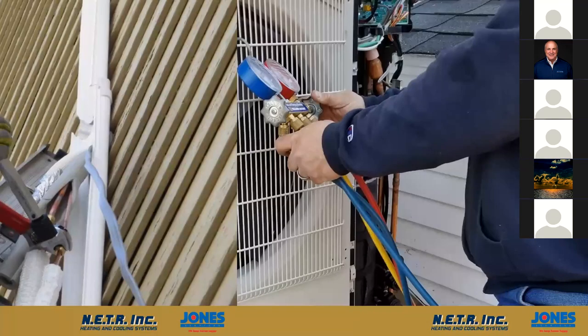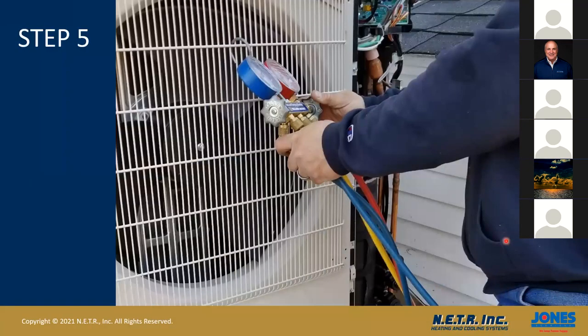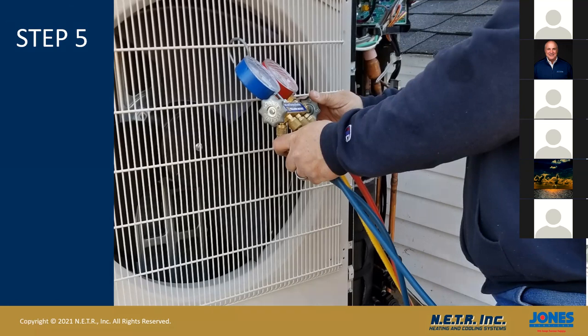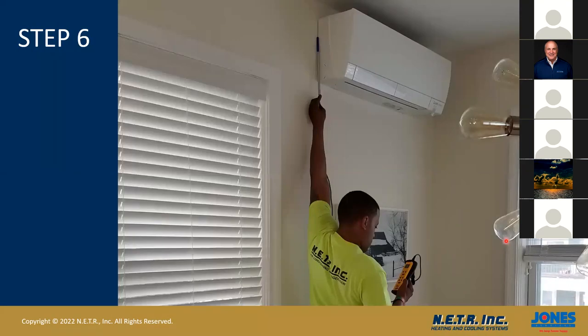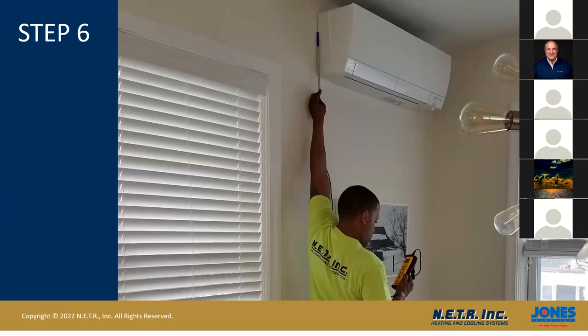Step five is the evacuation and the charging of what's going to happen. You're going to see a technician pressure testing things and monitoring pressure to make sure that the lines hold the pressure. You're going to also be seeing, again, here's that high efficiency unit that the gentleman hung. You can see he's doing some testing of air. Some return air temperatures, you can see right here. Here's that little sensor I was talking about. You can see he's measuring some temperatures in the room. So that's your six-step process on a one-on-one system. If there was multiple systems, there would be some things going on there.